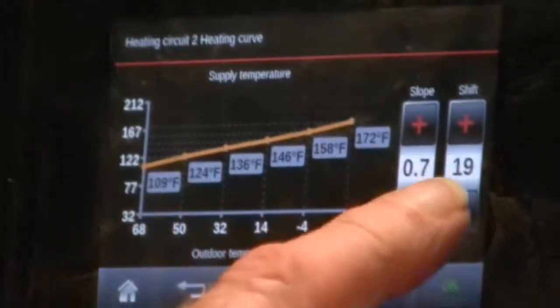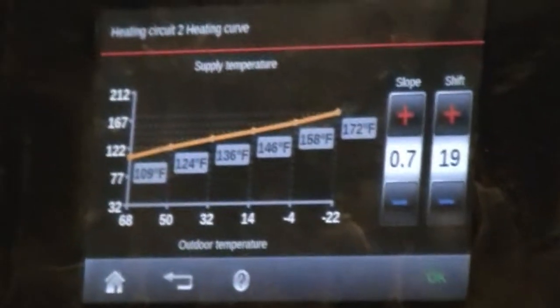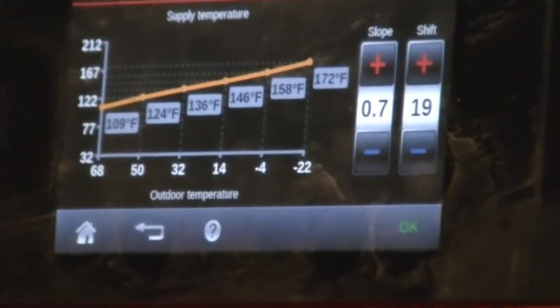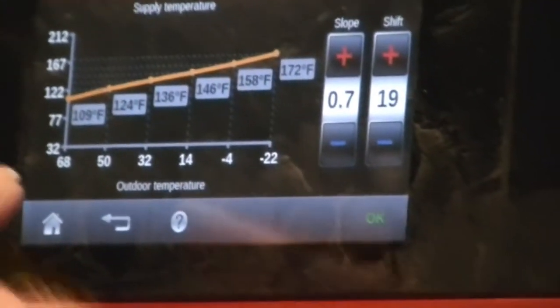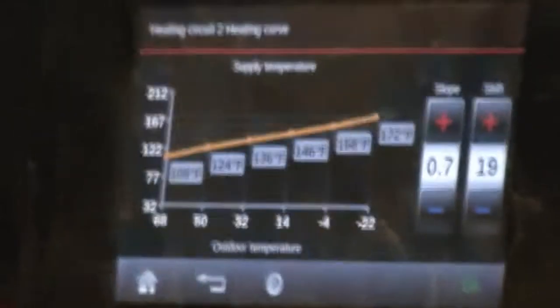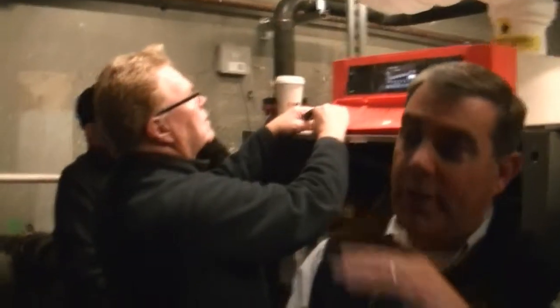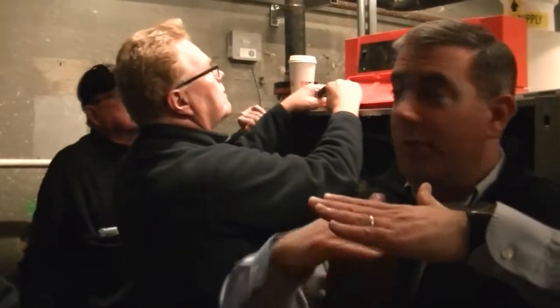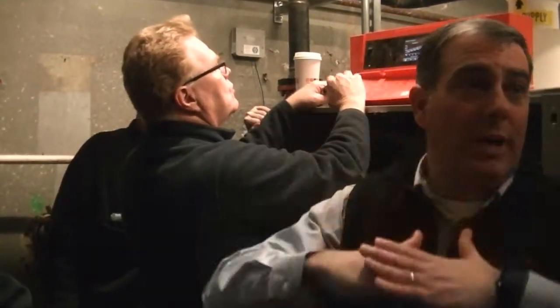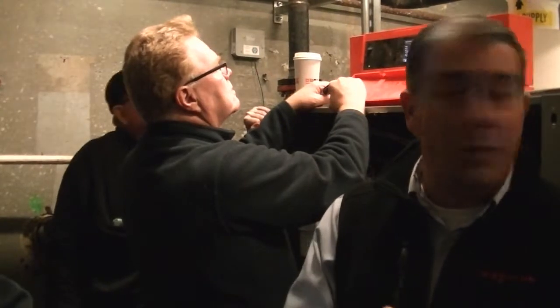So now, shift and slope are the same? So the slope is the pitch of the curve. So you have two different things. You have the heating curve, which is this line here. Now the lower that number becomes, the flatter that curve is. If you had a 2.0 heating curve, that would be a pretty steep hill. So you can actually now pick a flat curve, and with a shift, you can shift that curve up and down anywhere you want.